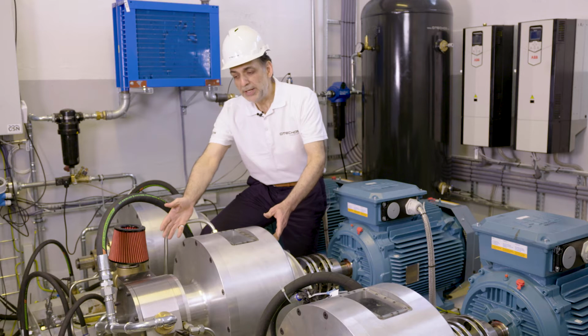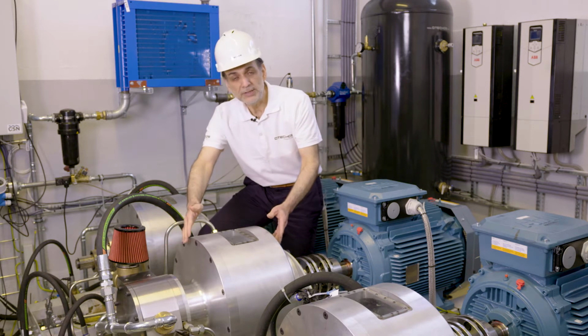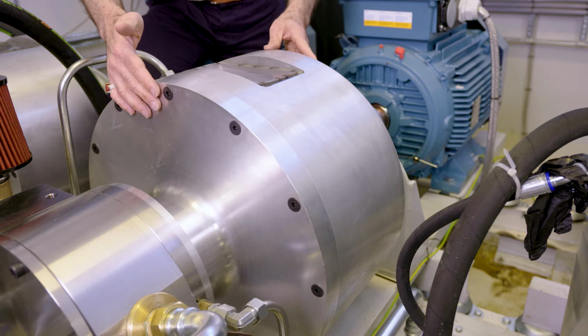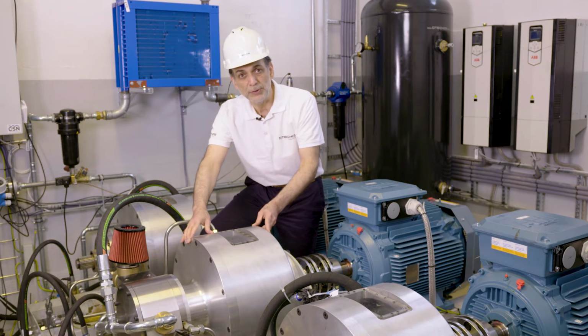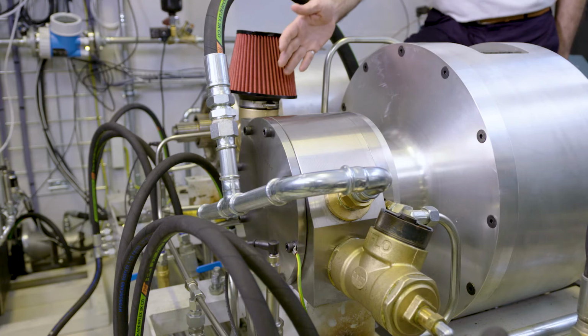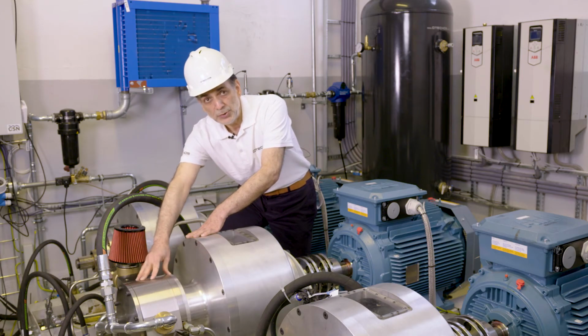This is the air end of the CRC, which is made of two sections. One section is the control unit, where a number of circular and elliptical gears are at work to produce the variable angular velocity for the rotors, which are inside the process unit here. The process unit is where the actual pressurization of air takes place.